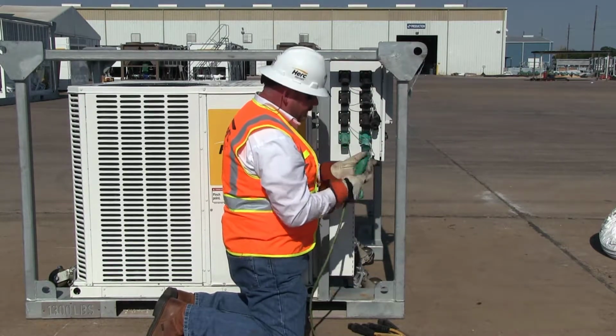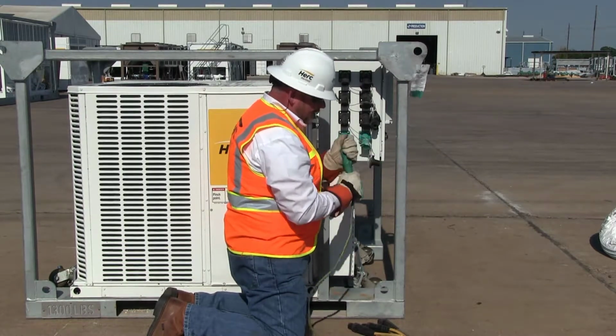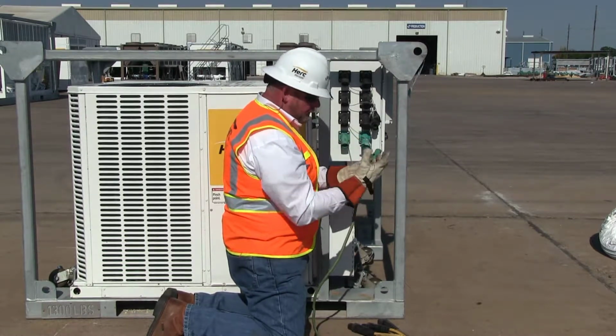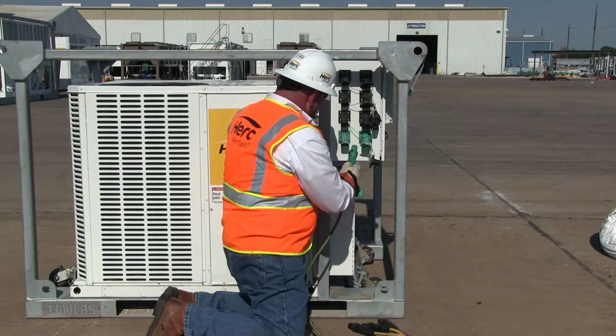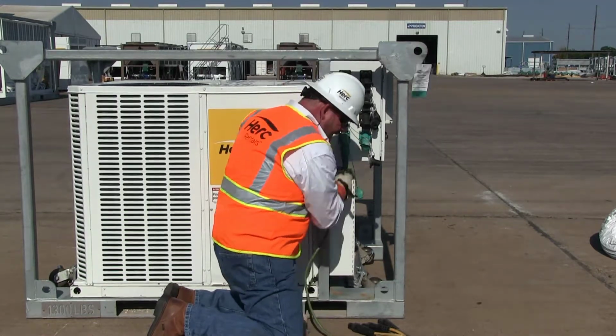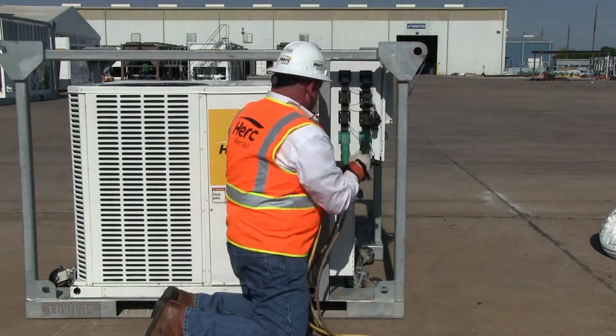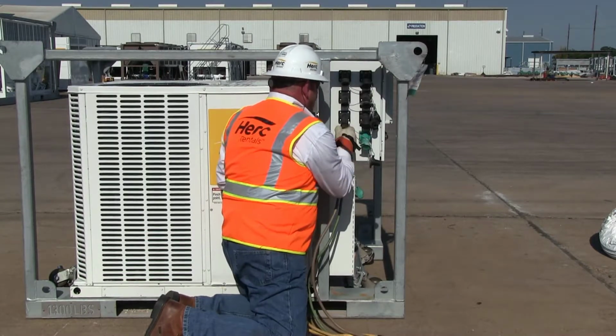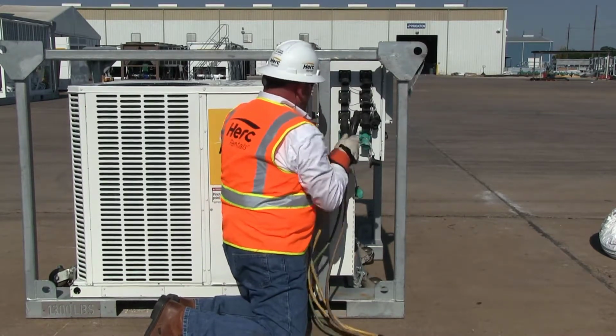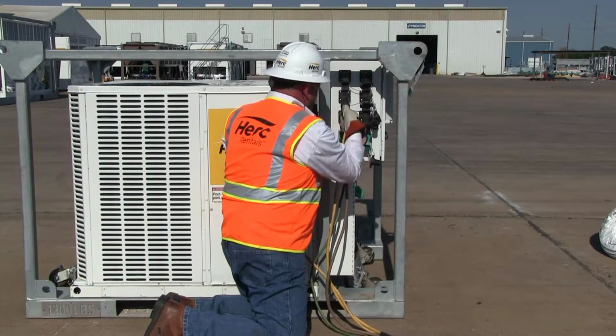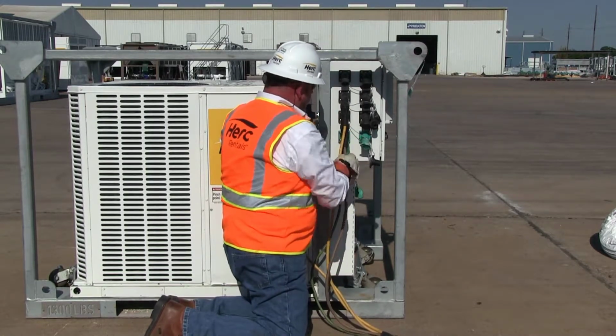The first thing you want to do is check the condition of each one of the cam locks, make sure the wire's in good shape, make sure you're wearing the proper PPE, and you always want to hook your ground up first, then followed by your L1, 2, and 3. And these simply are just standard cam locks that go in and lock in. Each time you go in, you want to make sure your cables are good and tight.